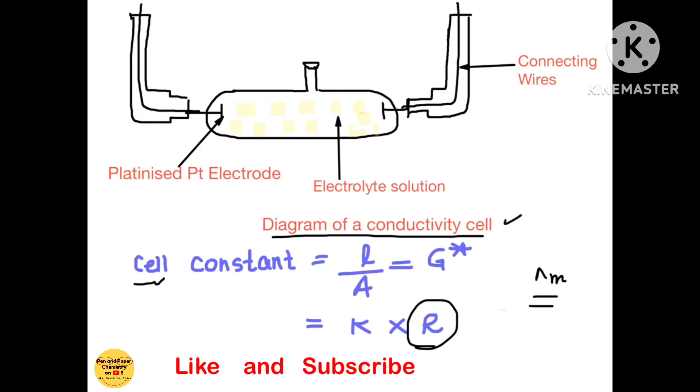Coming to the parts of a conductivity cell. We have a glass tube here. This glass tube is filled with the solution of the electrolyte whose conductivity is to be measured. We have two electrodes over here. These are platinized platinum electrodes. Platinized means coated with a very fine powder of platinum. It increases the surface area and also reduces the polarization effect.